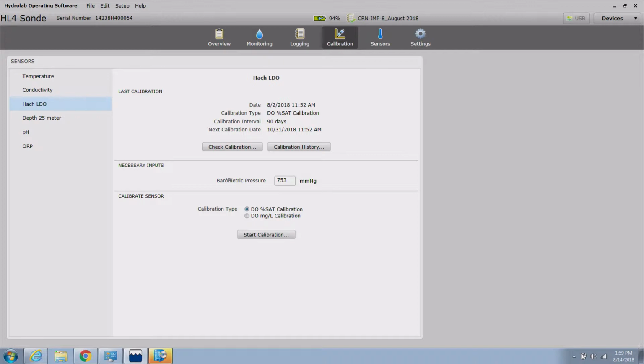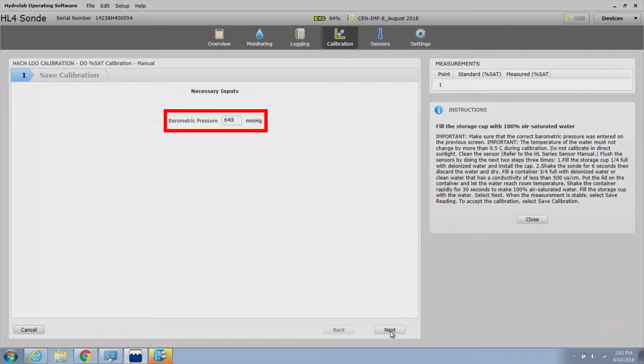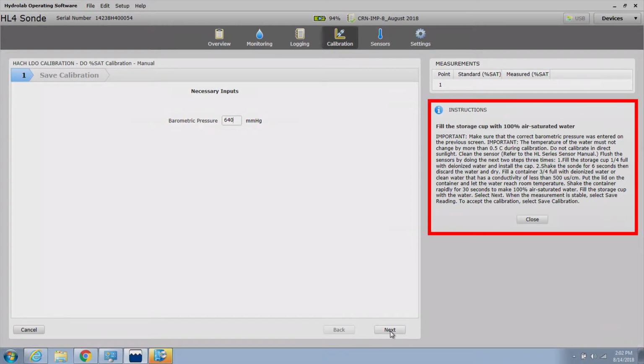Manually enter the barometric pressure of the calibration location into the barometric pressure text box. Click the Start Calibration button at the bottom to begin the LDO sensor calibration. Verify the barometric pressure to proceed with the calibration. For additional guidance, on-screen instructions are available on the right-hand side of the screen.